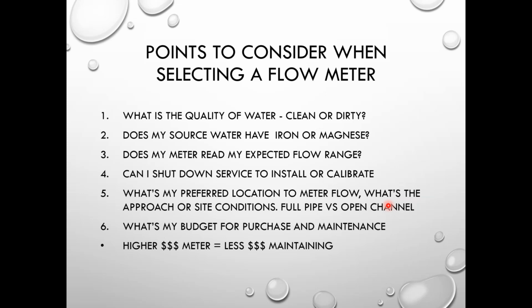Does my source water have iron or manganese? The reason we ask that question is because a lot of your mag meters have a hard time with high iron and manganese contents, and those will require cleaning a little bit more. And does my meter read my expected flow range? So we ask what's the lowest and what's the highest expected flow range, so we can pick a flow meter that will fall within that range.